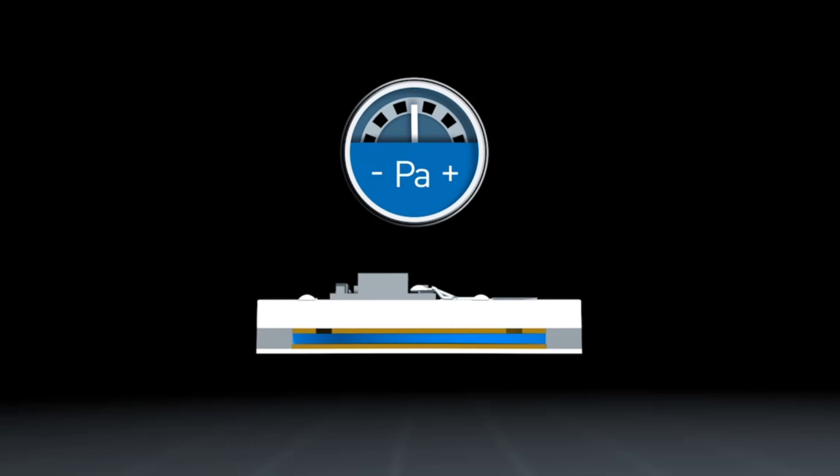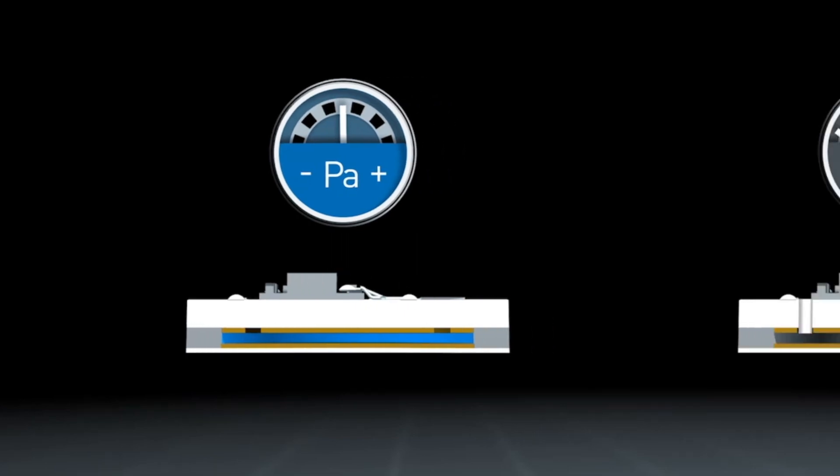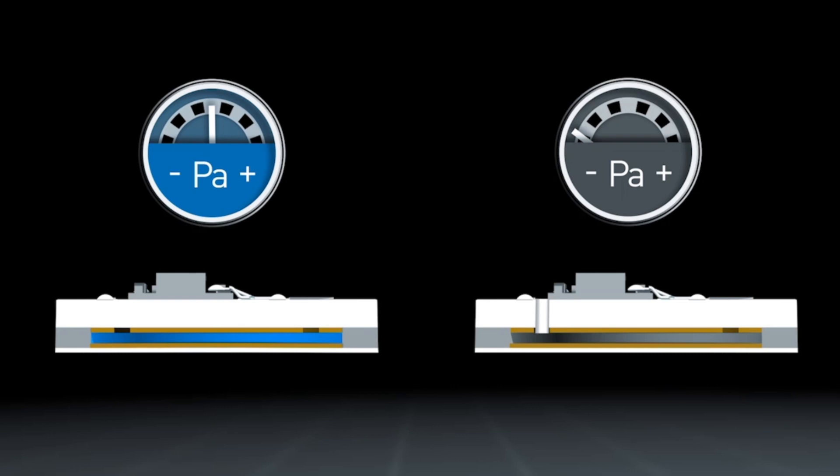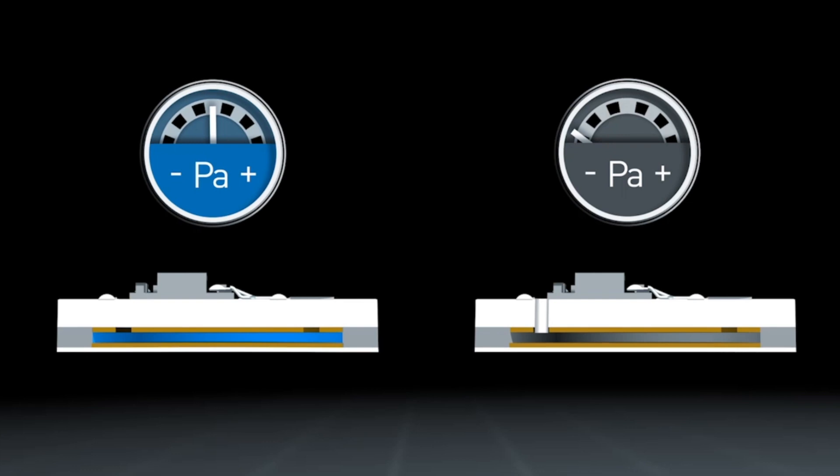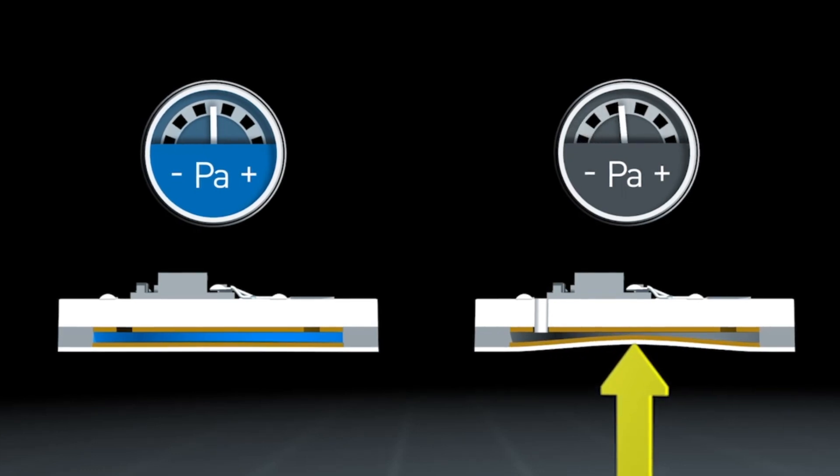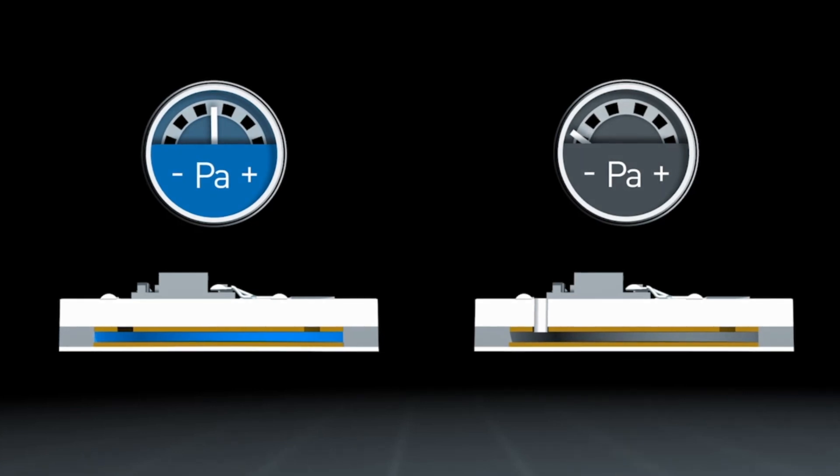The absolute pressure cell is a closed system and measures against the vacuum. In an atmospheric environment, the air pressure is indicated. In a gauge pressure cell, an opening in the substrate permits the pressure compensation between the atmospheric environment and the inside of the cell. The cell measures values which are relative to the ambient pressure. In an atmospheric environment, the air pressure is not indicated.